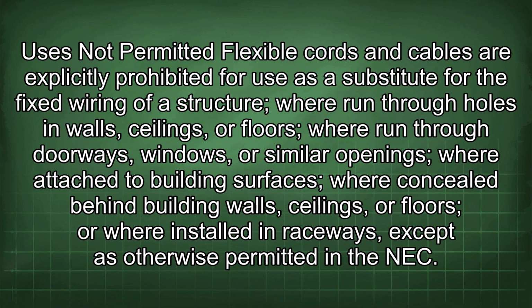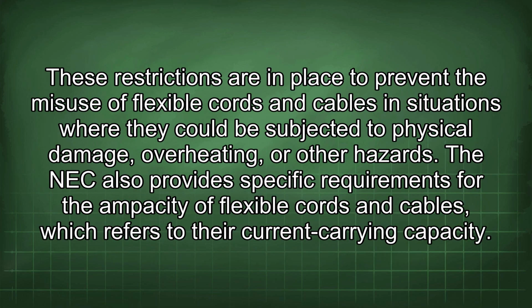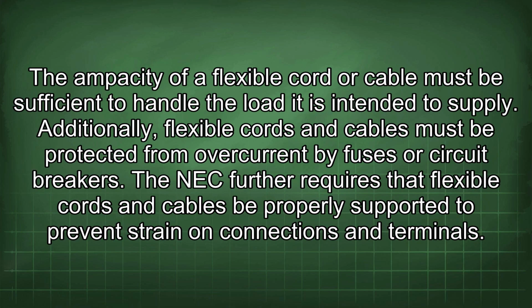attached to building surfaces, where concealed behind building walls, ceilings, or floors, or where installed in raceways, except as otherwise permitted in the NEC. These restrictions are in place to prevent the misuse of flexible cords and cables in situations where they could be subjected to physical damage, overheating, or other hazards. The NEC also provides specific requirements for the ampacity of flexible cords and cables, which refers to their current carrying capacity. The ampacity of a flexible cord or cable must be sufficient to handle the load it is intended to supply. Additionally, flexible cords and cables must be protected from overcurrent by fuses or circuit breakers.